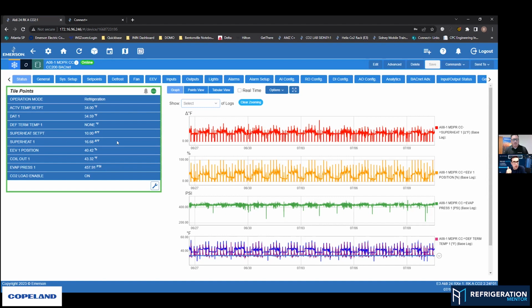I'm assuming he wants to go make sure all the wires are landed properly before even touching the controller. They land all the wires going in, like your temperature, your suction line, your return air, your supply air, making sure they're all in the right locations. What would be the next step?